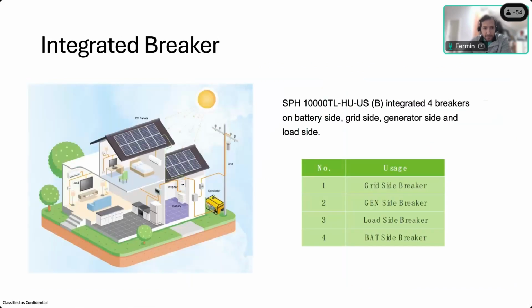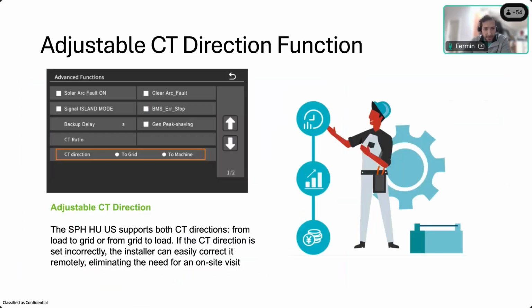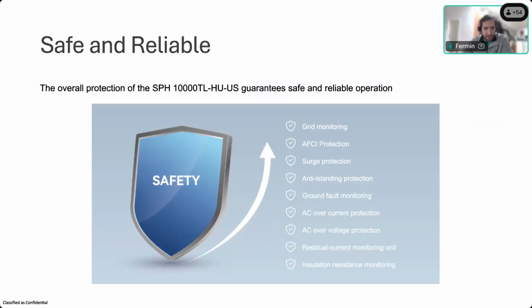It also comes with integrated breakers. There are 4 integrated breakers, 1 on the battery side, 1 on the grid side. There's a breaker for the generator and the load side as well. The SPH allows you to adjust the CT direction. So whatever direction you install the CTs, you can adjust that from the inverter screen. It comes with all the safe features: AFCI, UL 1699B certified, AC over current protection and over voltage protection, GFCI as well. So it's a very safe system.